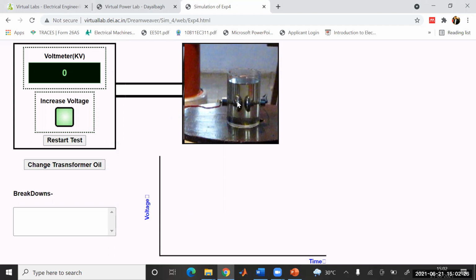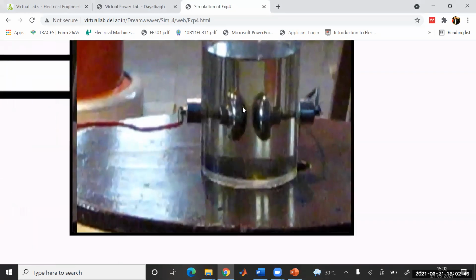So this is the entire test kit, as we have studied in the manuals. This is your controlling unit, this is your test unit, and this is your test vessel, made of glass or plastic fiber. These are the electrodes, spherical in shape, and the gap should be around 2.25 mm.